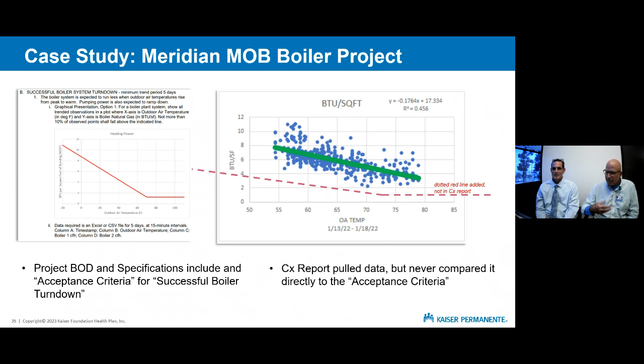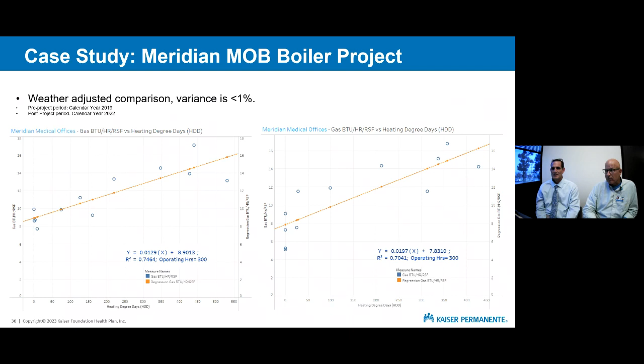So this is the weather-adjusted energy comparison pre and post project. The variance is about 1%. So we replaced the boilers. We've got much more efficient boilers, but we're not really saving any energy, most likely because of turn down, and we didn't do anything in the zones.